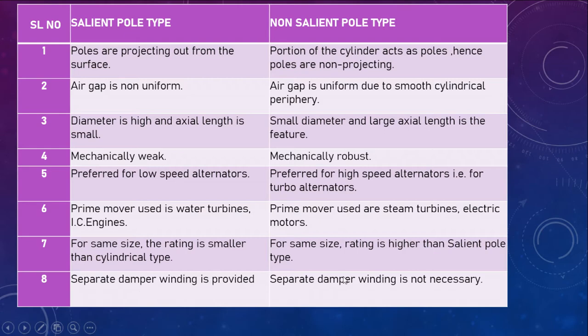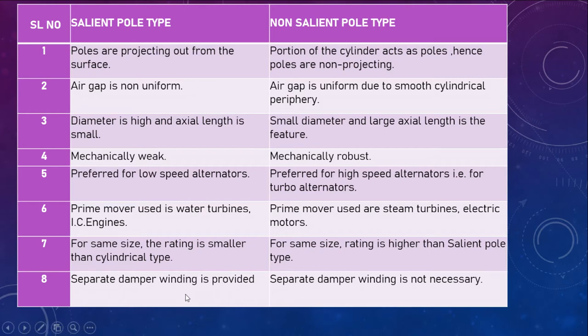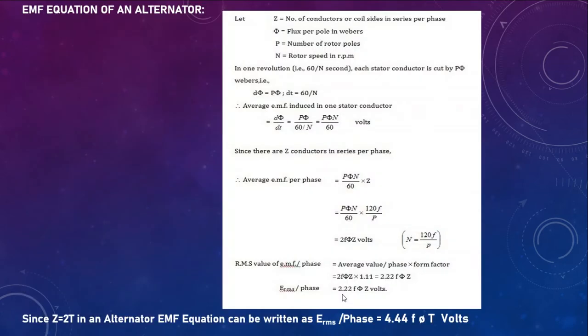Separate damper windings are provided in salient pole type rotors, but they are not necessary in non-salient pole type rotors. In salient pole type, a damper winding is provided to avoid hunting — that is, fluctuation in the output voltage. The provision of damper winding is not necessary in non-salient pole type rotors.